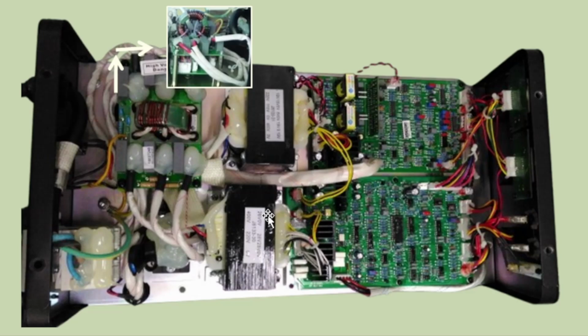Wire feeder PCB communicates with wire feeder and also takes crater voltage and current values from front panel potentiometers. 2 front panel switches send gas check and 2-stroke 4-stroke signals to wire feeder PCB. Power and fault LED are also connected. Finally processed signals are sent to control PCB. Control PCB takes inductance set value from the front potentiometer. Welding current and voltage values are displayed on the front panel 7-segment displays. Control PCB sends gate signals to power PCB for IGBT gate driver.